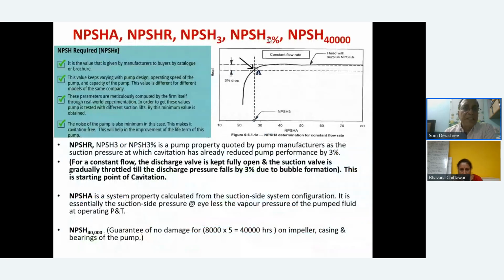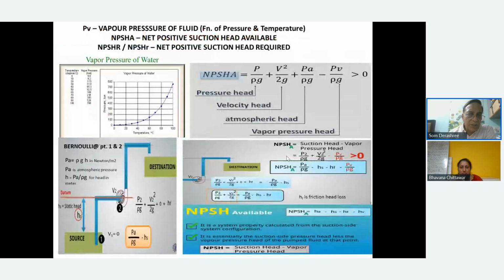Now, what is NPSH? Again, on terminology, there's one more terminology, which is NPSH 3 or 3%. You will come across this also, which is given by the manufacturer. Now, this is a property quoted by the pump manufacturer, the suction pressure at which the cavitation has already reduced pump performance by 3%. Now, how it is done is actually they will keep the pump on the test rig and keep the discharge valve fully open, so the flow is constant.